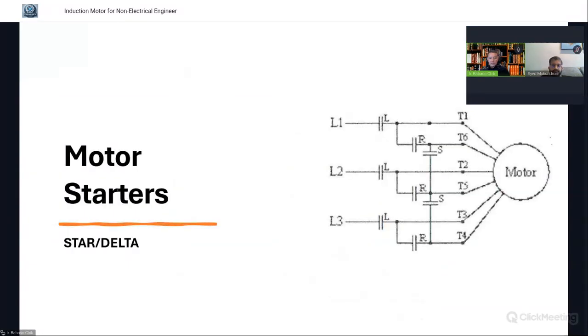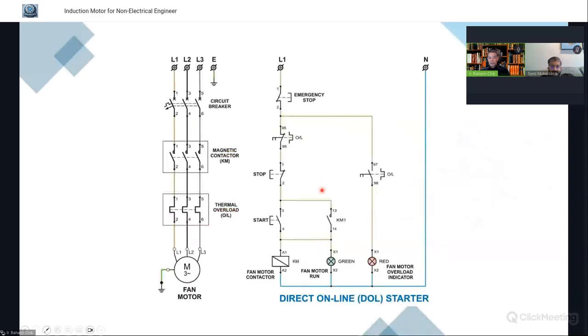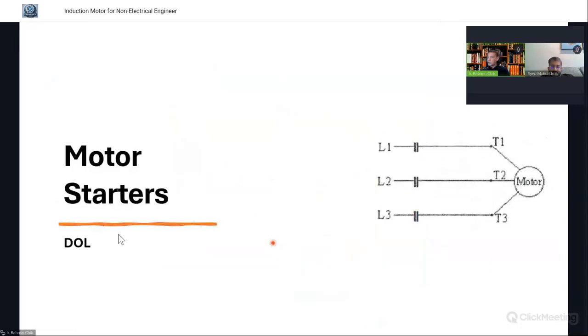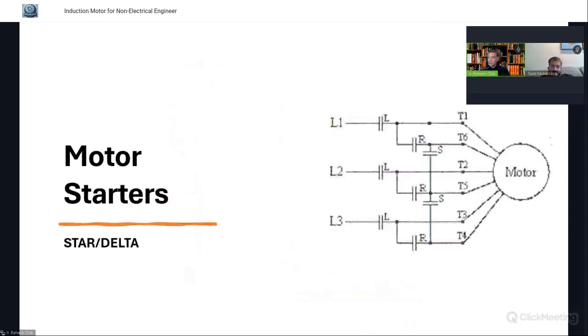This is a star delta. Like I told you just now, we have several contactors for the star and delta. Now, if you notice, there are 6 cables that need to be brought out from the motors, instead of what we saw for the DOL just now, which is only 3. For the star delta, we need to take out this connection so that we are able to connect the motors during starting with star, and after it runs, it needs to be connected to delta using timers.